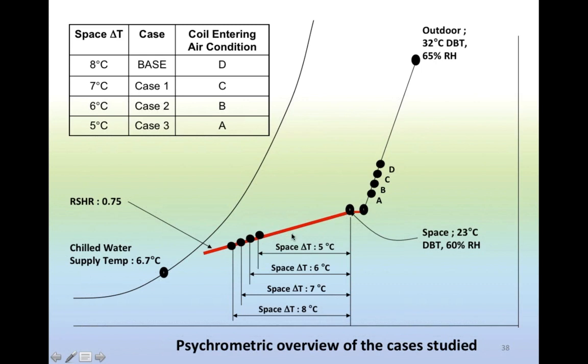The point I would like to highlight here is that at all these various possible operating conditions, space delta T of 5 or 6 or 7 or 8, you have to make sure that they end up on the same red line. That's the load ratio line of the room sensible heat ratio. That hasn't changed. Remember, we said that's an important design criterion. The further away you move from the saturation line to be on this line, the more challenging it becomes to achieve that condition. The simple reason being, for a cooling coil to come to a space delta T, say like this condition here, which I'm showing you as a space delta T of 5 condition, it has to overcool and dehumidify and then reheat itself to get to the right condition.